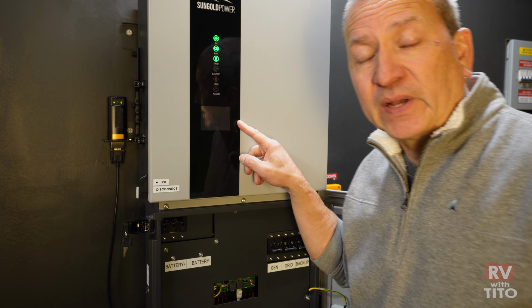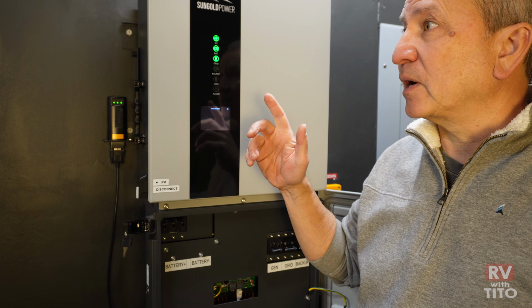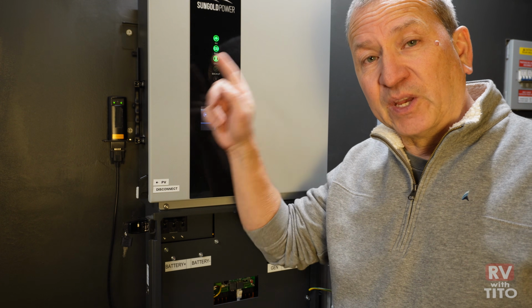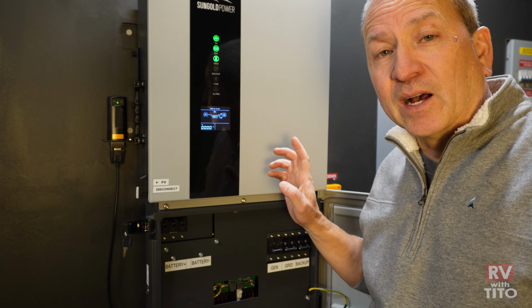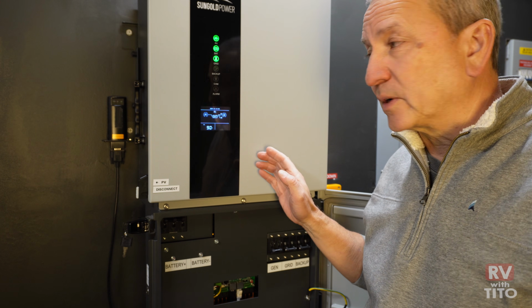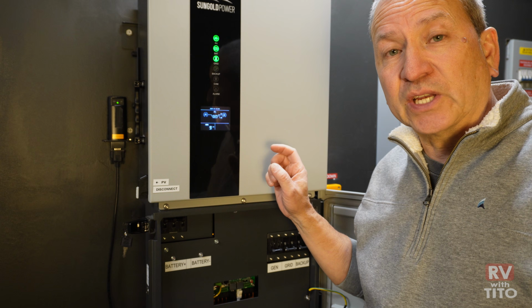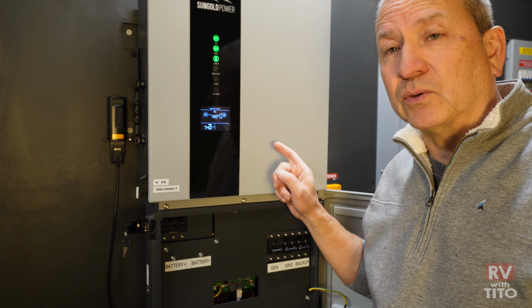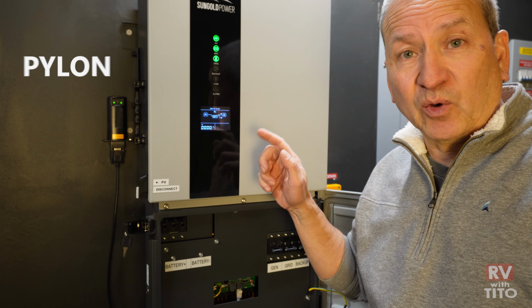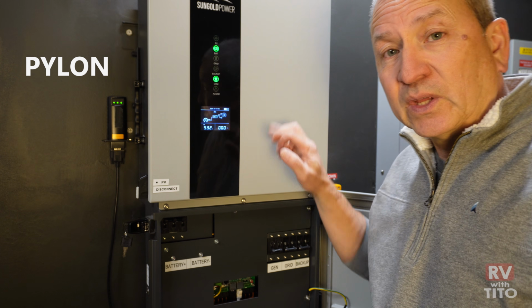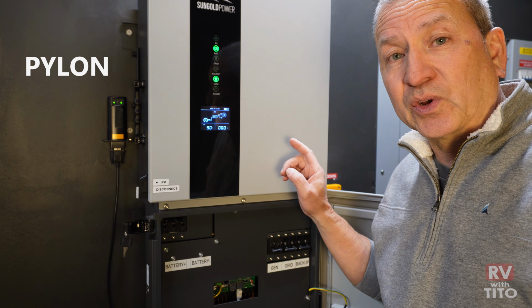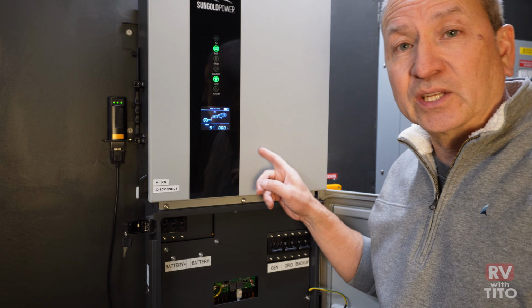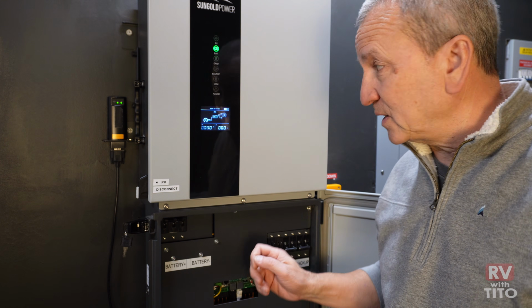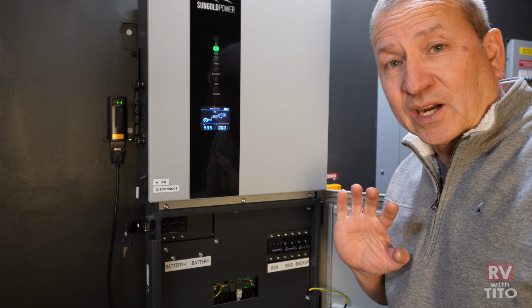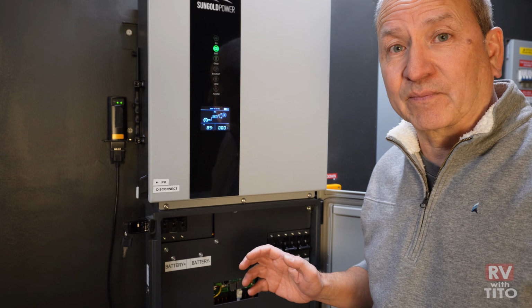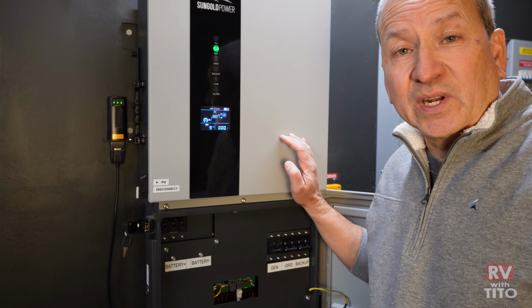While it's firing up, I should point out that if you're connecting your BMS communication using the CAN port, you'll want to set your BMS protocol to Pylon, P-Y-L-O-N, Pylon Tech. You should have a list of options for your particular inverter. Once you set it to Pylon and your cable's connected, your comms should just automatically come online, pretty easily.